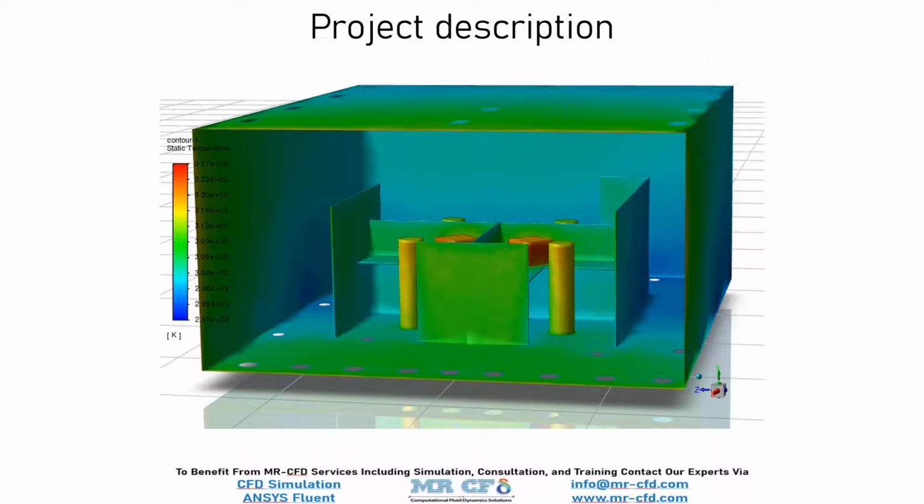In this project, steady airflow enters the domain from the bottom of the room by several inlets and exits the domain from several outlets on the ceiling, considering radiation heat transfer. This air conditioning method is new and is commonly used in office environments nowadays. This method provides more energy efficiency since the flow naturally goes upward due to the density difference and buoyancy body force.